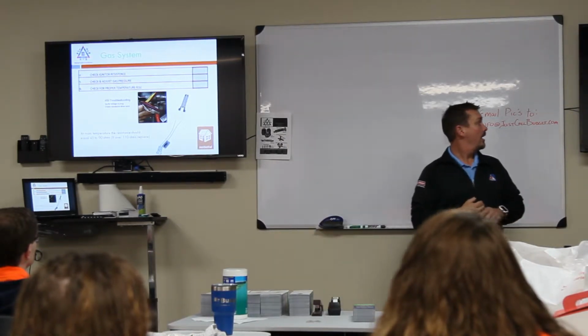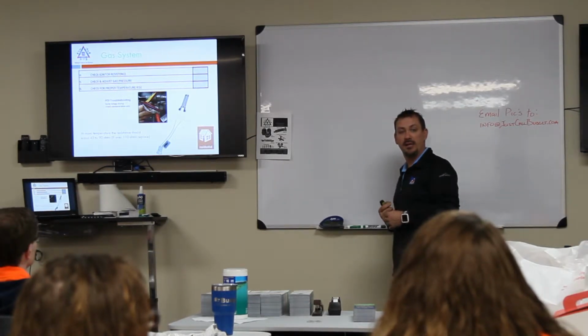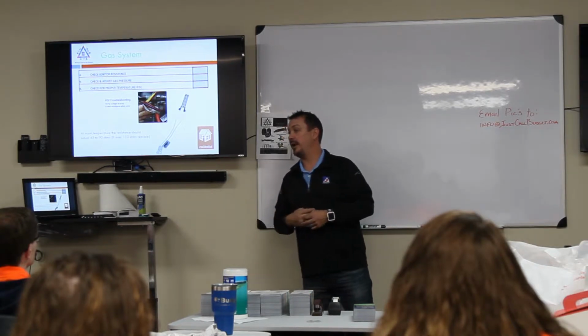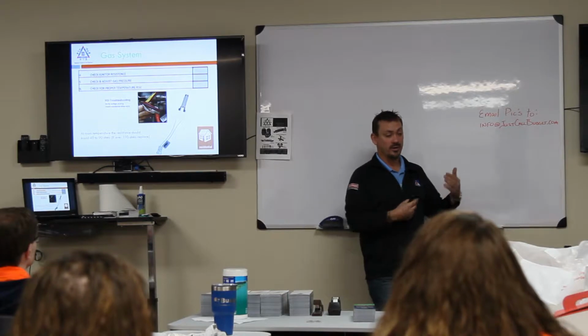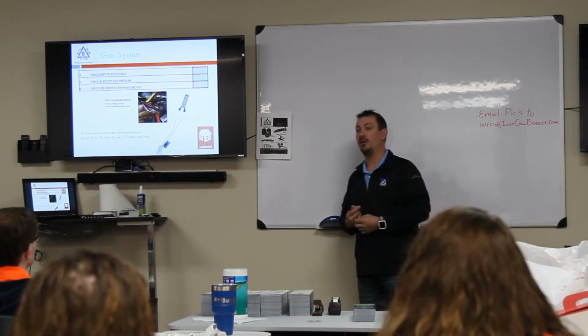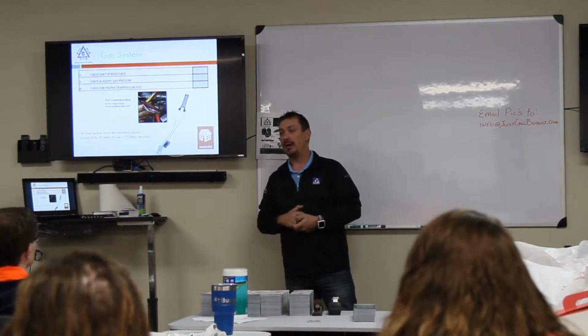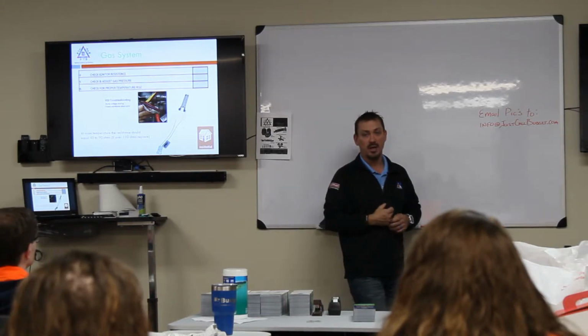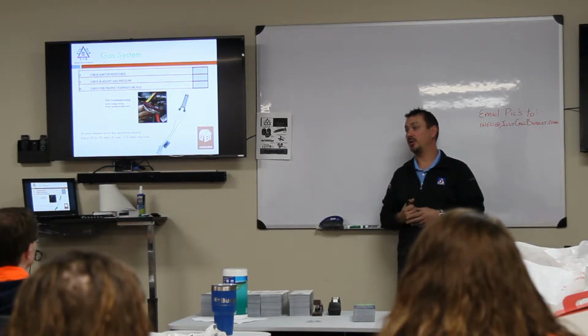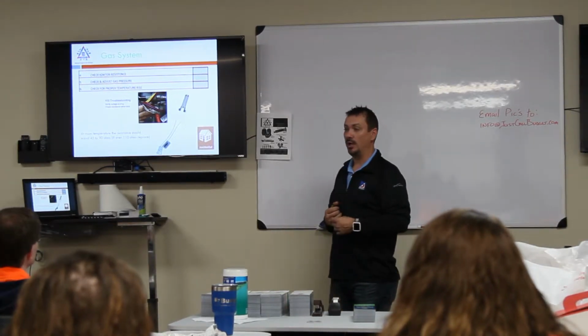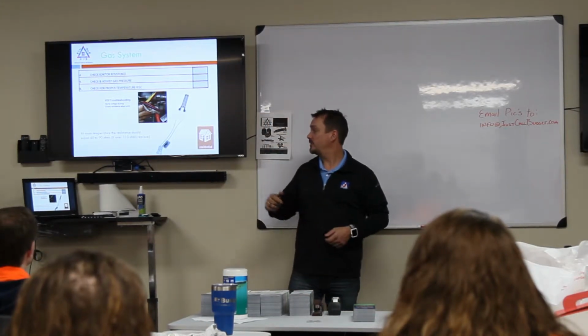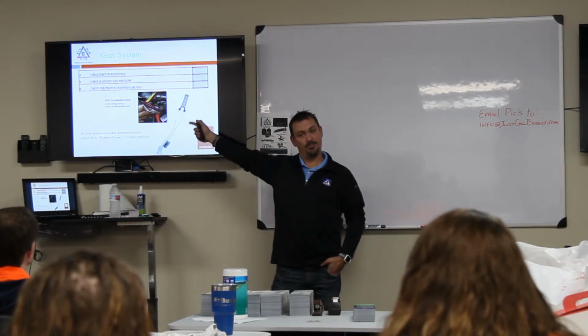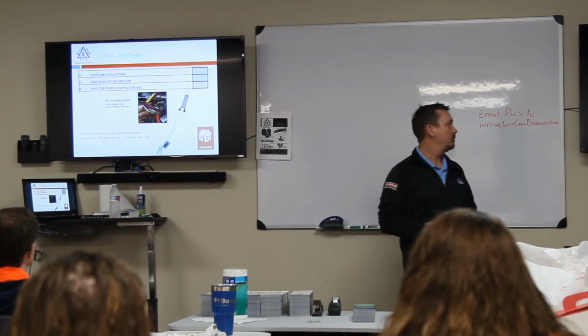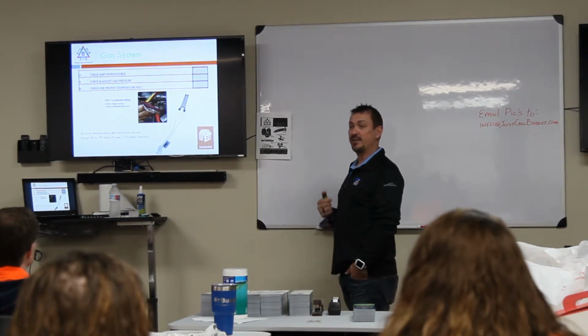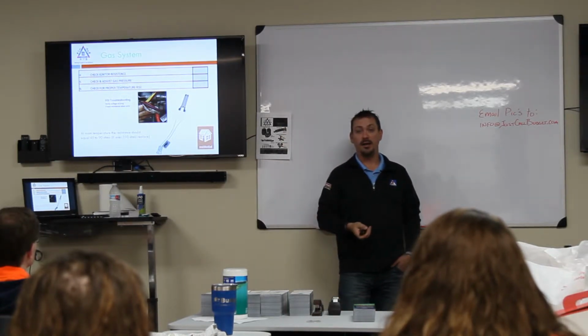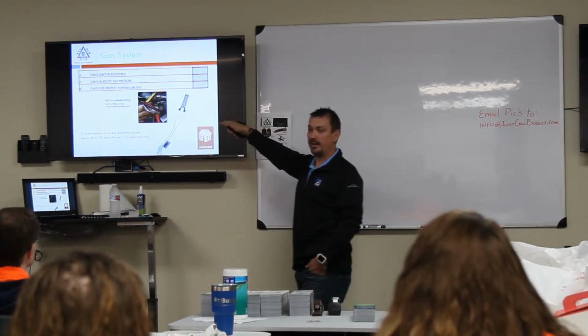On your igniters, you're going to check the resistance of the igniter. Every igniter has a certain resistance at room temperature for it to be at. So there are some charts out there for every different brand of equipment that you come upon, or any different brand of igniter that you walk up on. There is a different resistance between each one of those. I know Johnstone has some of the charts. You can find the charts online. Also, if you can't find them online, then give us a call. We'll get that chart to you. There's a chart that will show you, for instance, this brand right here, this style, at room temperature will ohm out between 45 and 90 ohms. If it's over that, that is a good time to suggest or recommend to that homeowner an upgraded igniter. Now, these carbide igniters, they're going away.